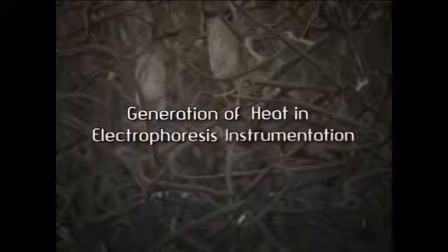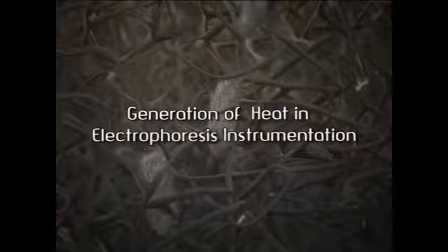Generation of heat in electrophoresis instrumentation. During electrophoresis, the power W watts which is generated in the supporting medium is given by W equals I squared R. Heating in electrophoresis causes a decrease of buffer viscosity, hence a reduction in the resistance of the electrophoretic medium. Thermal instability of samples that are sensitive to heat may lead to the denaturation of the proteins and thus the loss of enzyme activity.